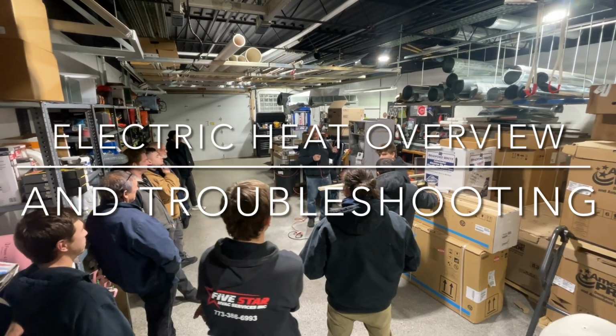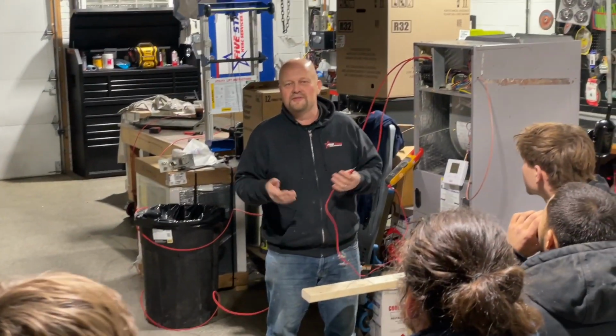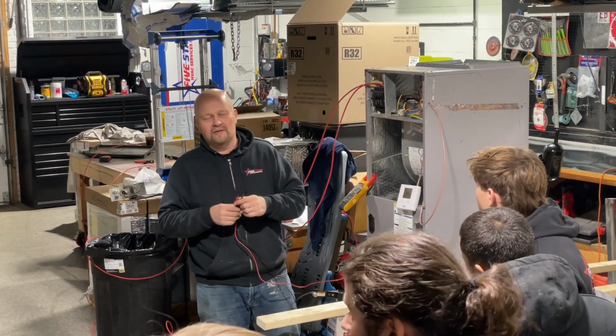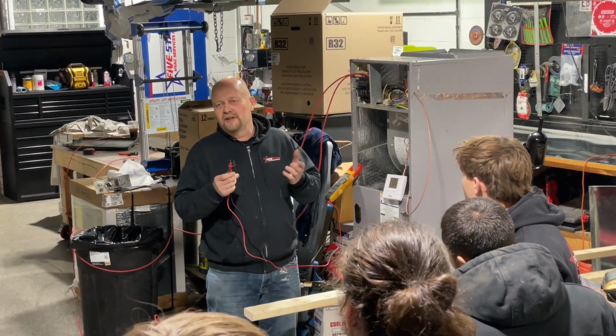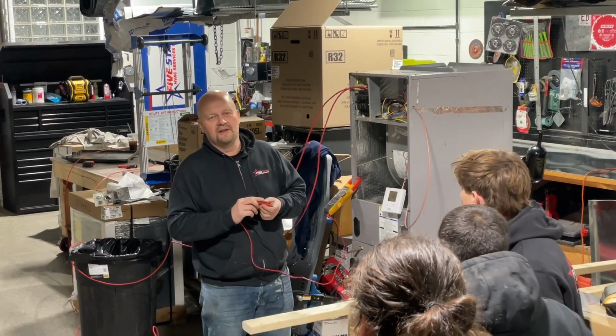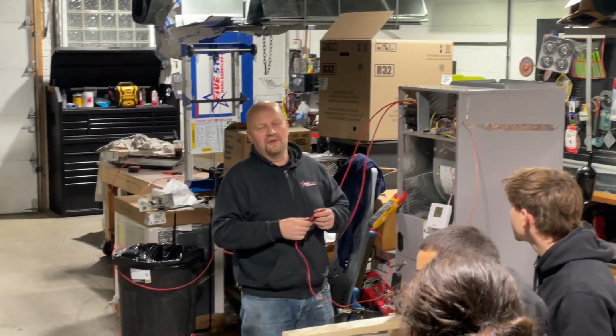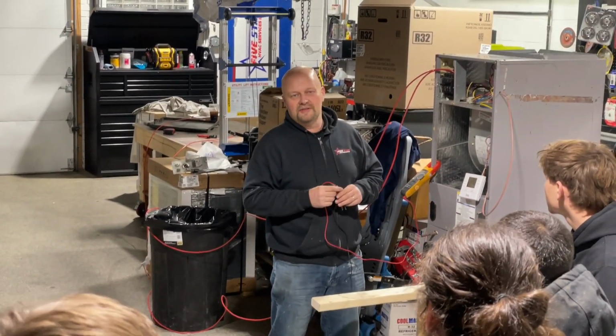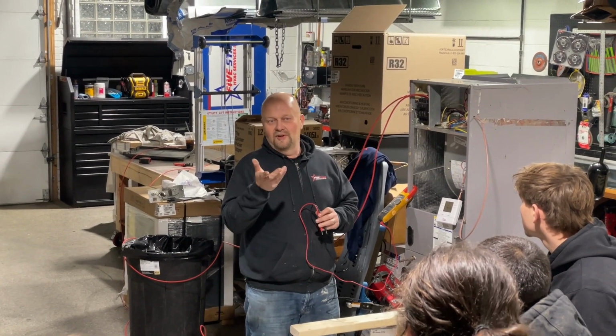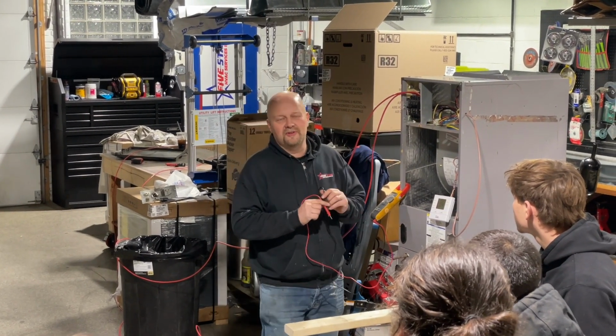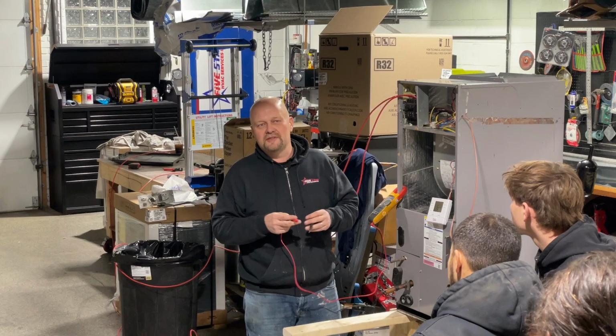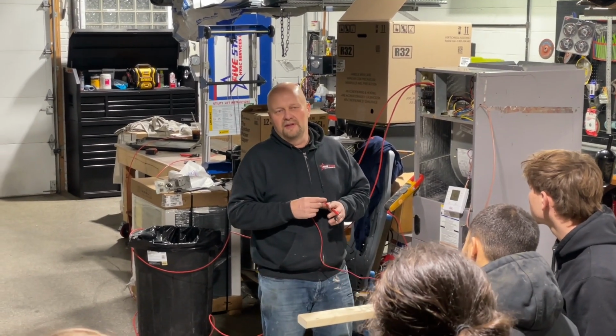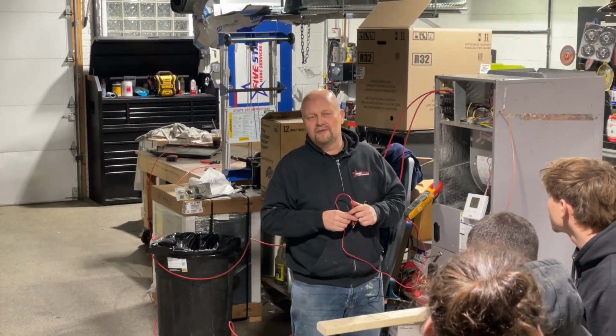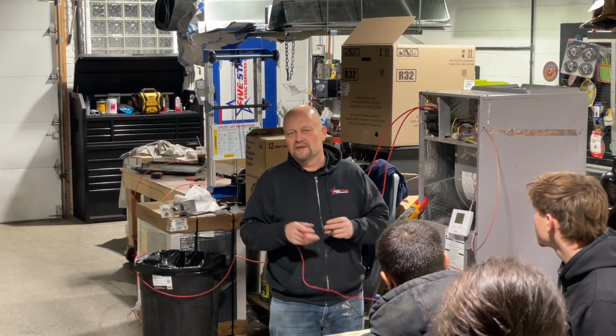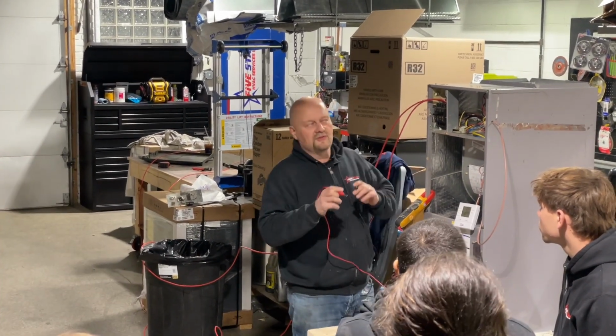Alright, my good friends, let's talk about an electric furnace. Very simple device. Only a few things you have to know, a few things you have to check, right? So, first thing, let's check what kind of voltage we're going to get. Matt, what typical voltage would you have on an electric furnace? 120 or 240? Well, 240, right? So 240 would be a typical voltage because something that's going to electrically heat is going to require a lot of energy. So for that we need two phases of 120 volts, so 240 volts total.